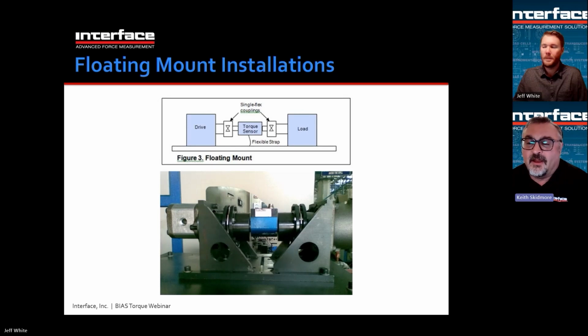So here is an example of a floating mount sensor installation where you have the blue sensor in the middle. You have a single flex coupling on each end of the shaft, and then you have a motor spinning through a plate, spinning the assembly, and you have a gearbox on the other side reacting the torque or creating the load. And the torque sensor hangs in the middle. And the only thing that keeps that housing from spinning along due to the bearing friction is a flexible strap, which again, in this case, is literally a tension spring held between a threaded hole in the sensor housing and the plate. So it allows it to articulate.